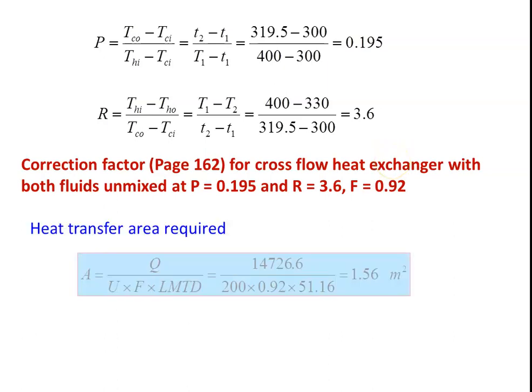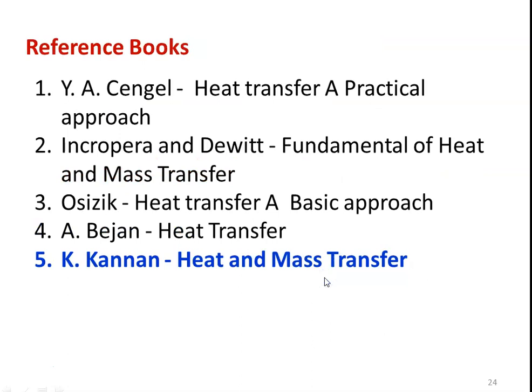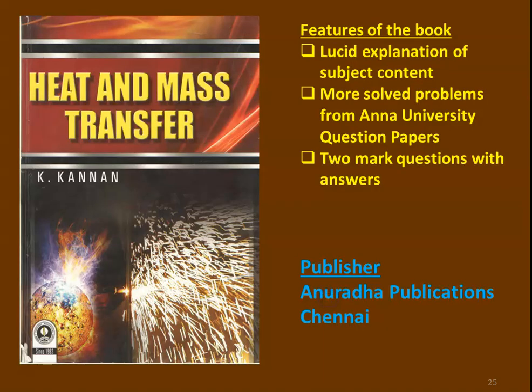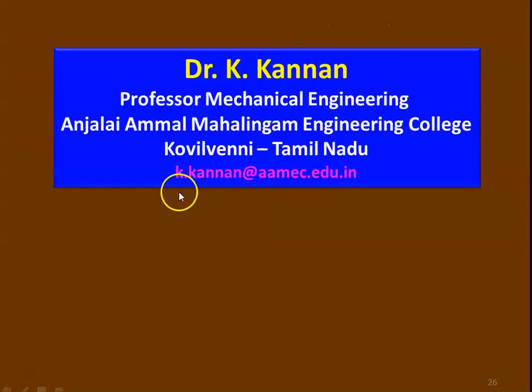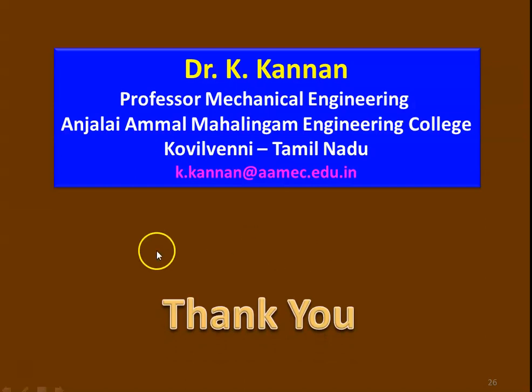Area required: A = Q/(U × F × LMTD) = 14,726.6/(200 × 0.92 × 51.16) = 1.56 m². This is the heat transfer area required for the radiator. These are the reference books used; you may refer to them for further details. The mail ID is given here — you can write for any clarification or doubts on heat exchanger design. Thank you, and we will meet again.